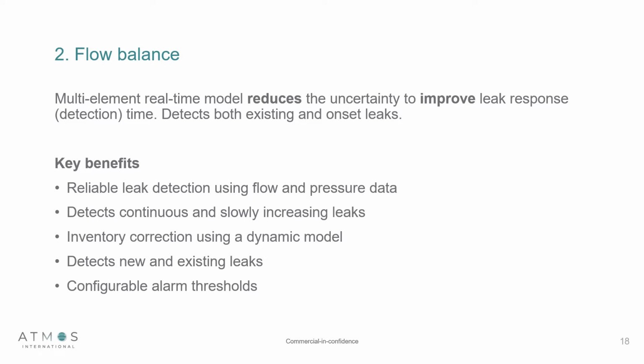So as I stated before in a couple of slides before, our flow balance system reduces the uncertainty to improve leak response time by using pattern recognition. And as stated before, it's very reliable in detecting existing leaks, continuous leaks, or slow forming leaks. And a flow balance system, very much as the Atmos Pipe system can, it can work in all scenarios, from transients to dynamic to static. The negative pressure wave, depending on the change in pressure, can have some difficulties in transient conditions.